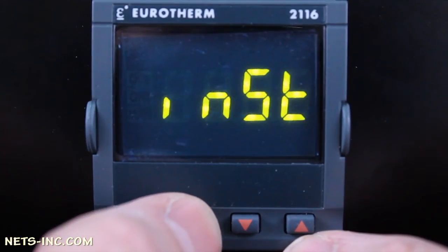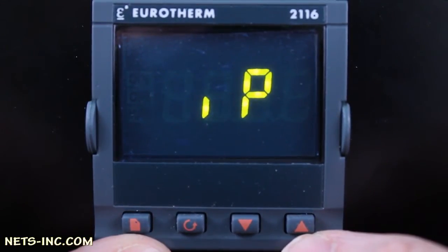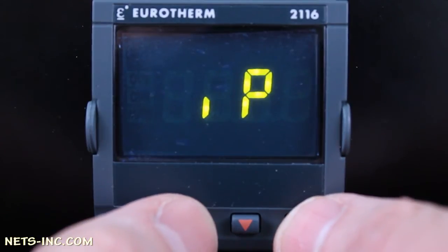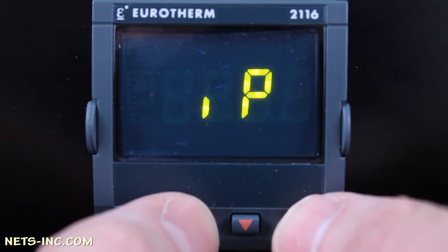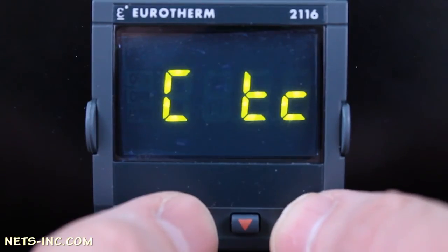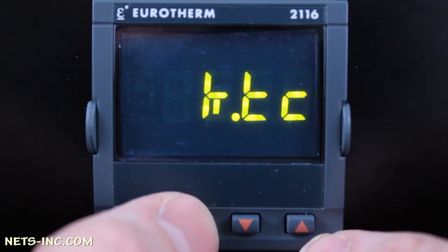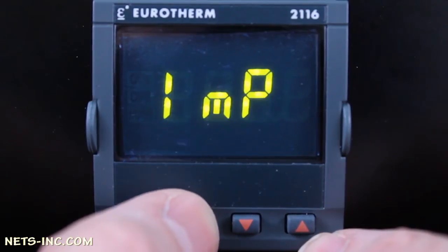Next, press the page key once to advance to the IP list. This is the area where you set up the type of thermocouple input sensor that you are using. For this example, we will be using a type K thermocouple. Press the scroll key once and the display will read INPT. Press the up arrow until you change the display to read K.TC. Press the scroll key repeatedly until the display reads IP once again.